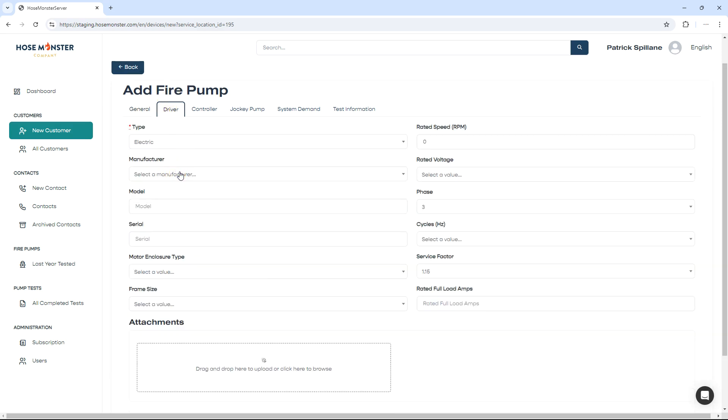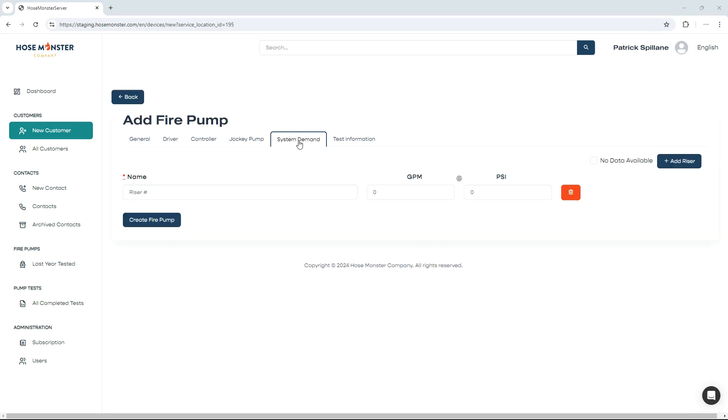Under Driver, you must also choose whether it's electric, diesel, or other. Under System Demand, please enter the hydraulic information for the risers that the fire pump is feeding. This is important because we want to make sure that the fire pump is properly meeting the flow and pressure requirements of the most demanding systems. This information will be graphed on our discharge graph in the fire pump test report.